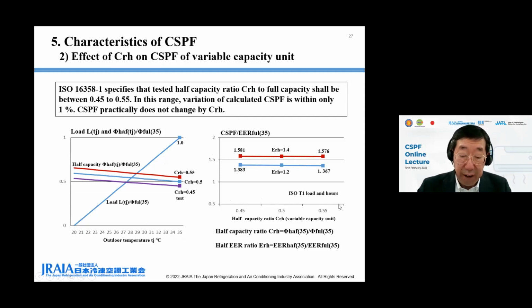This page shows the effect of half capacity ratio CRH on CSPF of variable capacity unit. ISO standard specifies that tested half capacity ratio CRH to full capacity shall be between 0.45 and 0.55. Usually, manufacturers have test modes to fix the inverter frequency for full and half capacity tests so that the capacity ratio becomes within this range.